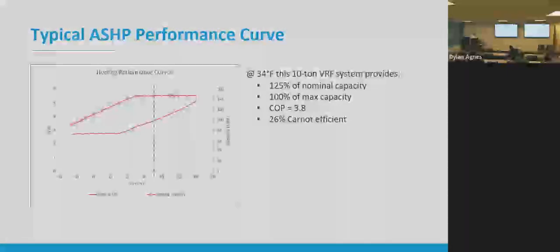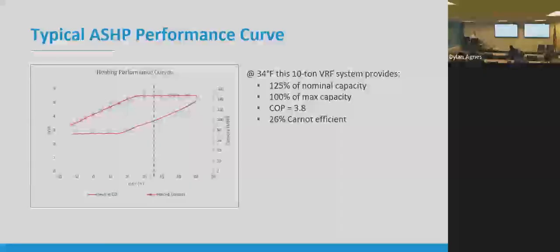Here's a performance curve of our office building. I have the best details on it, but it's not a cold climate VRF system. It's about 10 tons, just kind of off the shelf VRF from 5-6 years ago. At 34 degrees, where that blue dashed line is, we have 125% of nominal capacity, so close to 12 tons, 150 MBH. 100% of max capacity. That's as much as it can deliver. And its COP is about 3.8, so it's 26% of Carnot efficiency.